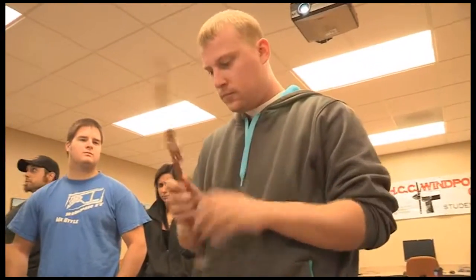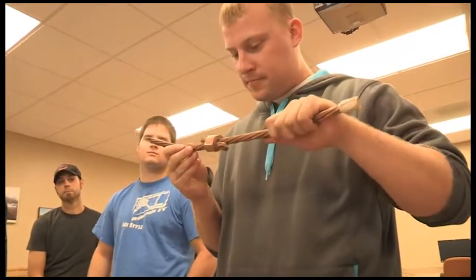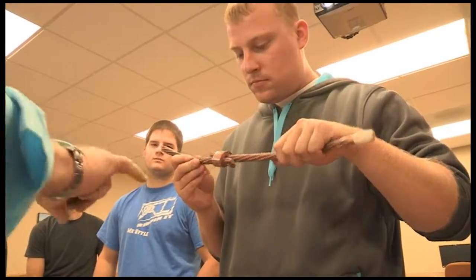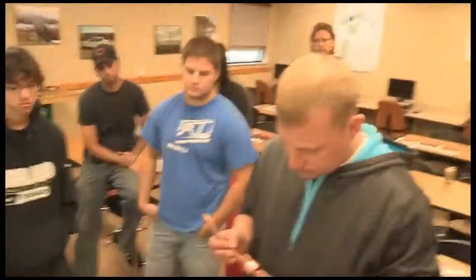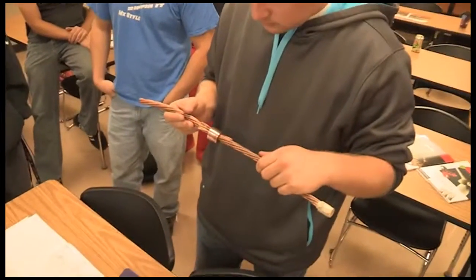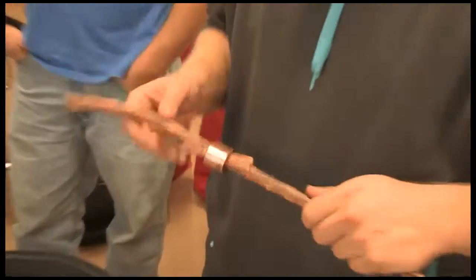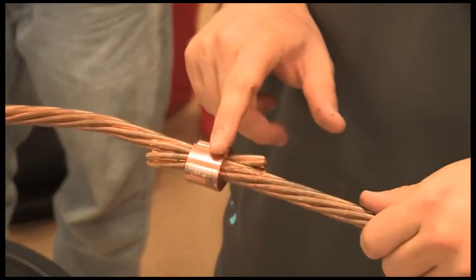And then you look at it to make sure that you got the embossment. What number are we looking for? 997. Yep. And that'll verify that we used the right connector. We got the right cable sizes. We got two 4-aught cables. And we used the right die with the right tonnage to get that embossment.